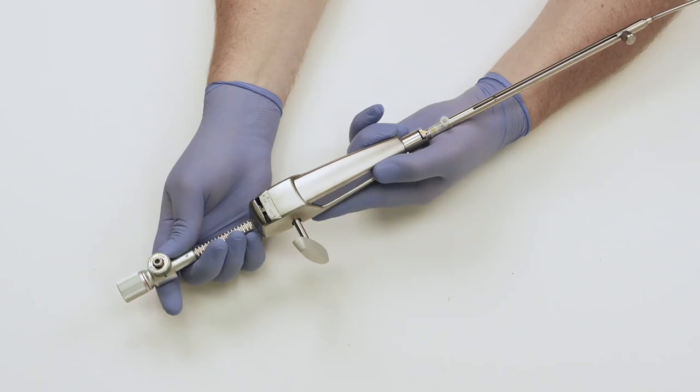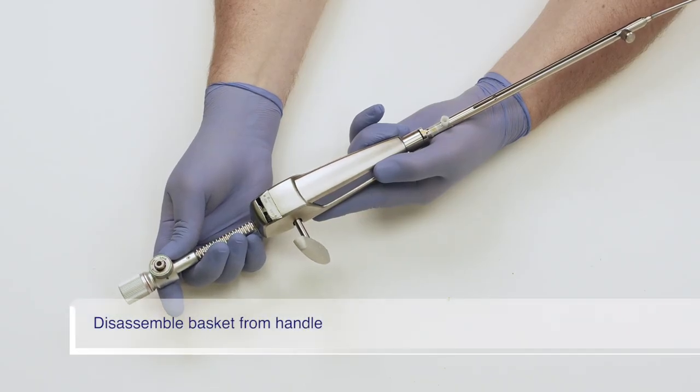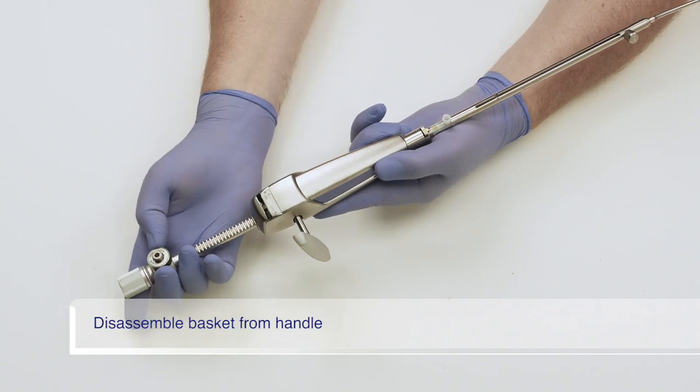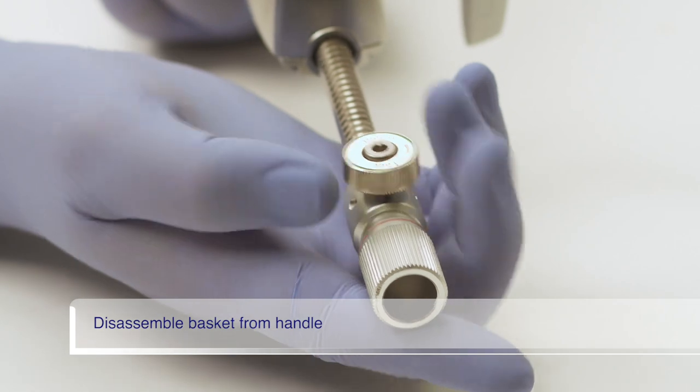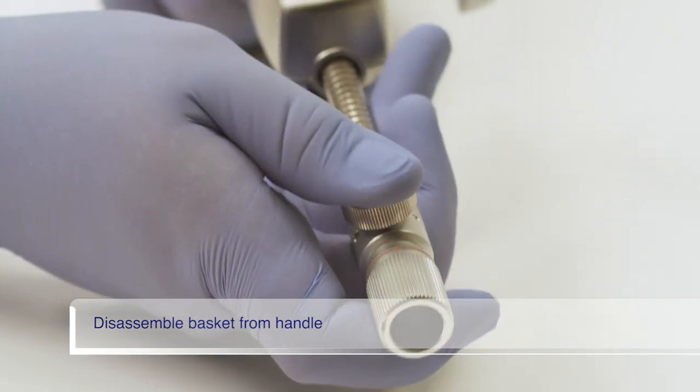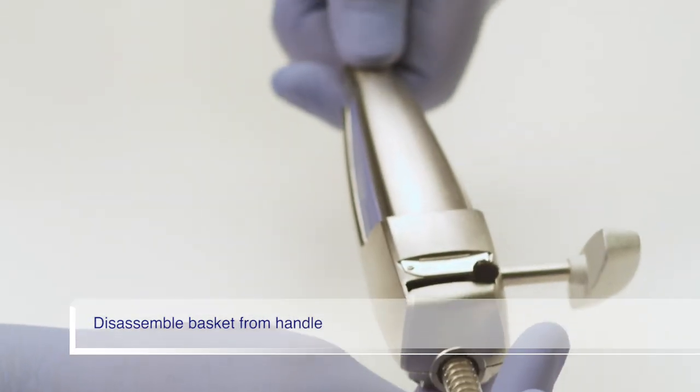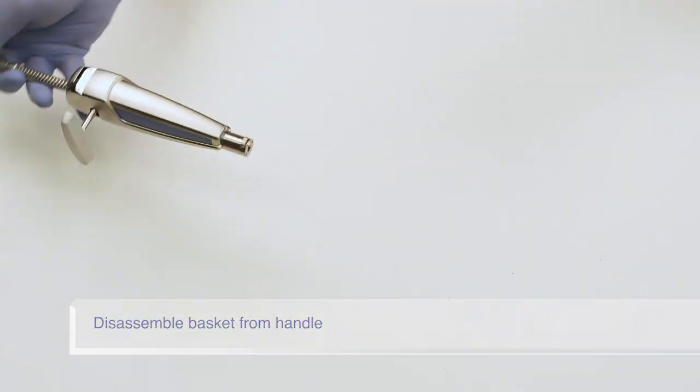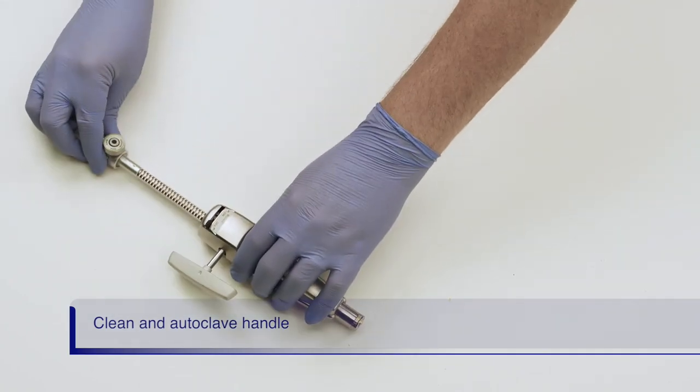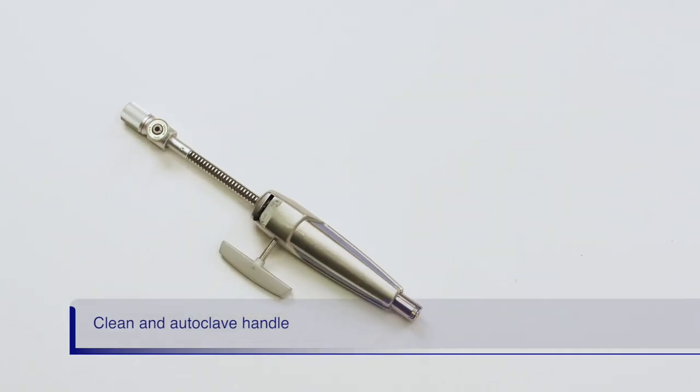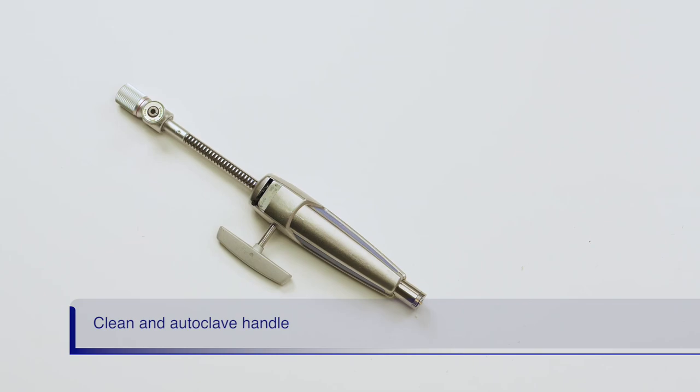Now that we are done crushing the stone, we need to disassemble the handle and basket. First, loosen the release button by turning it counter-clockwise, and then push the release button and yellow button simultaneously while pulling the handle away from the basket. After the procedure, dispose of the basket. The handle is reusable and needs to be cleaned and autoclaved.